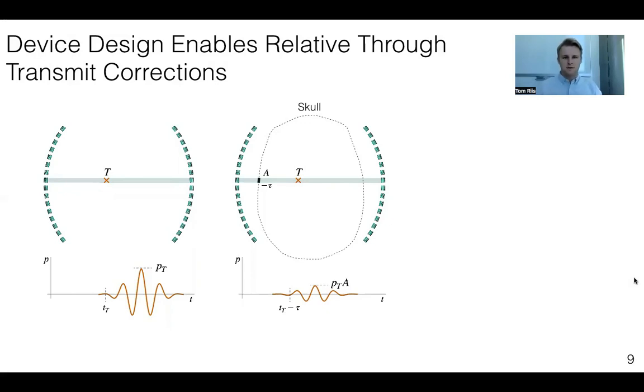The way this method works is that we take through transmit measurements. So these are measurements where we emit a brief pulse of ultrasound from an element on one of the transducer arrays, and we record from all other elements on the opposing transducer array. We take these through transmit measurements both in water and then with the device actually applied to the subject. And from the difference in these two measurements, we can show how the presence of the subject's skull is distorting the incoming beams of ultrasound and then correct for them.